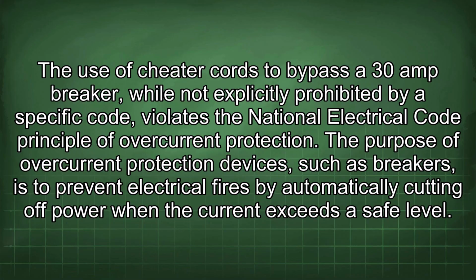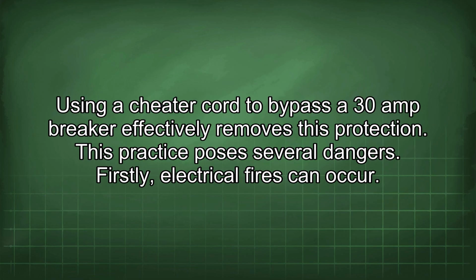The use of cheater cords to bypass a 30-amp breaker, while not explicitly prohibited by a specific code, violates the National Electrical Code principle of overcurrent protection. The purpose of overcurrent protection devices, such as breakers, is to prevent electrical fires by automatically cutting off power when the current exceeds a safe level. Using a cheater cord to bypass a 30-amp breaker effectively removes this protection.